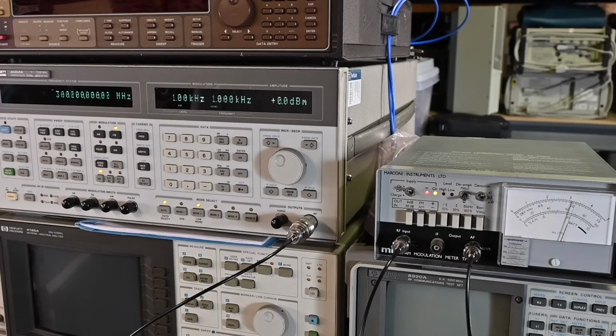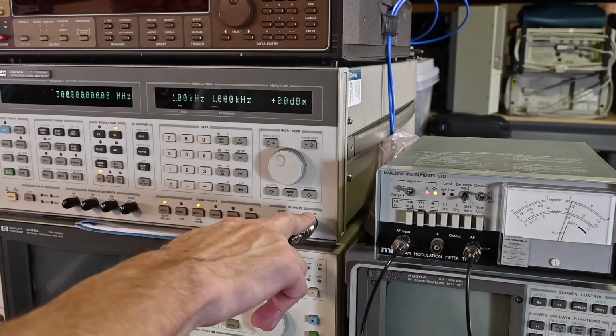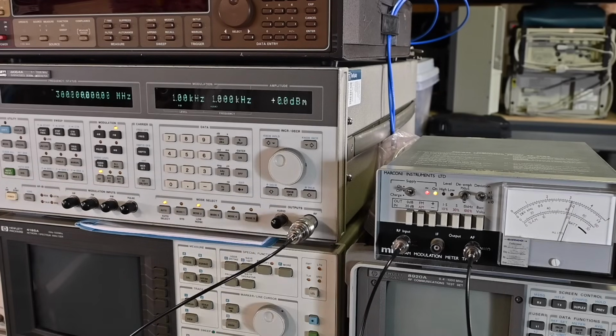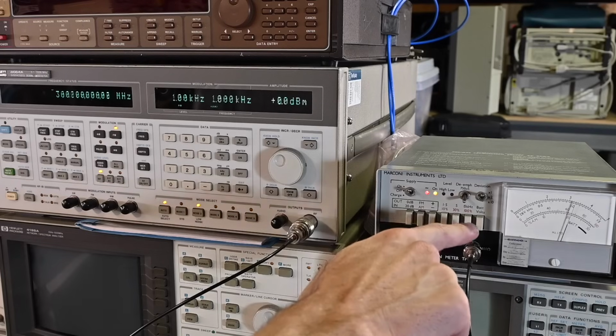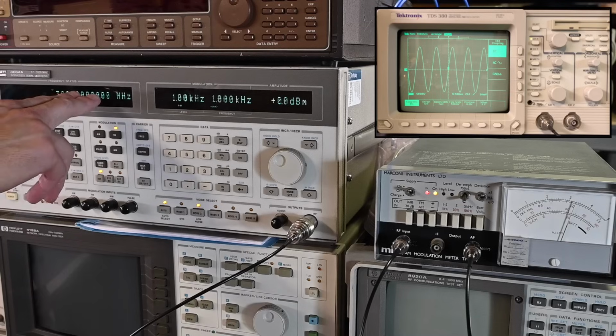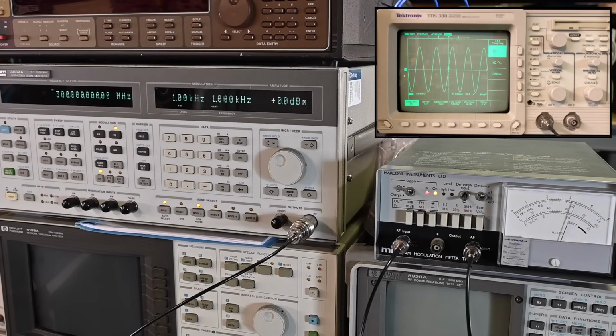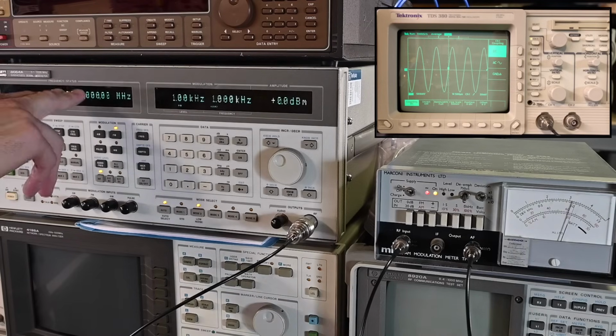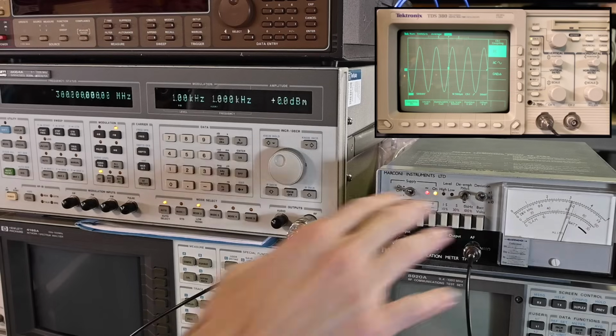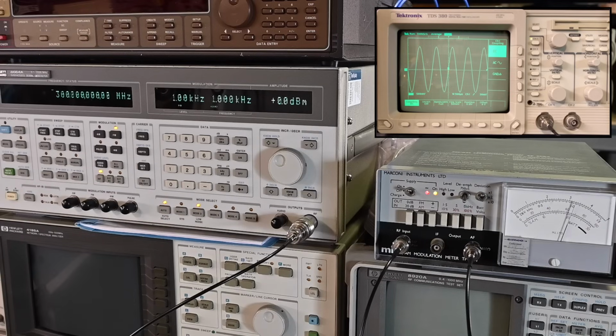All right, so let's take a look at what's not working correctly on the modulation meter. You can see I have the RF output from the signal generator connected to the RF input on the modulation meter, and the demodulated audio signal is going over to the oscilloscope. Right now the signal generator is on 300 megahertz, that's the carrier frequency, and it doesn't matter what this frequency is set to, as long as it's within the range of the modulation meter, it doesn't affect the problem. I'll change this to a couple different values and you'll see the effect.